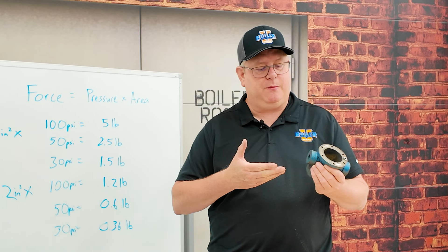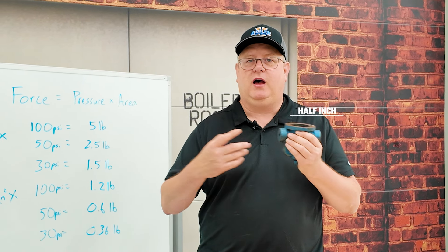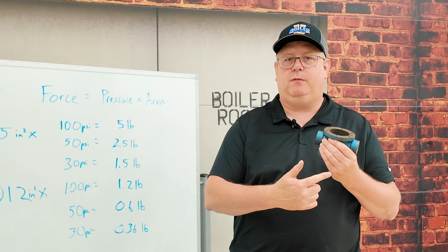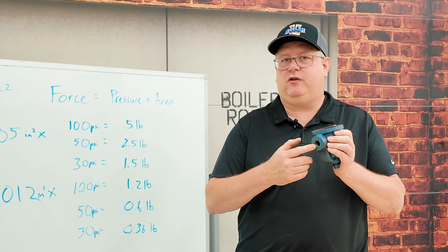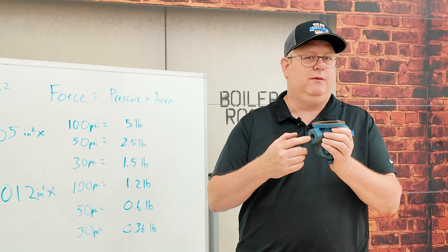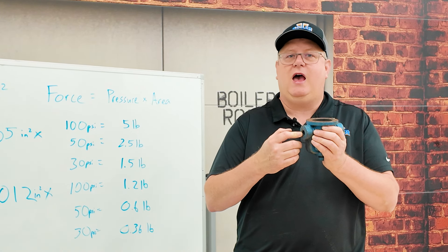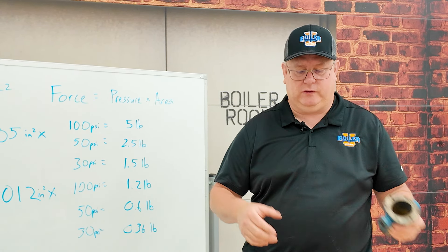If I was going to replace this particular trap, I could easily say, oh it's a half inch trap, I've got one in the parts crib. But the piping connection on a trap is not the limiting factor for capacity. Actually, it's the internal orifices.